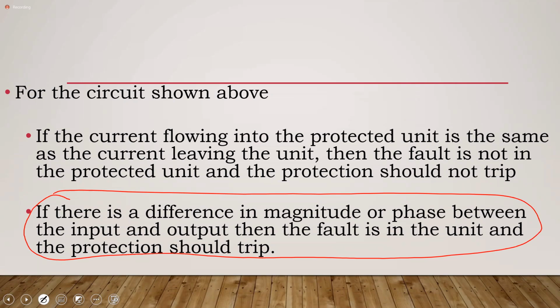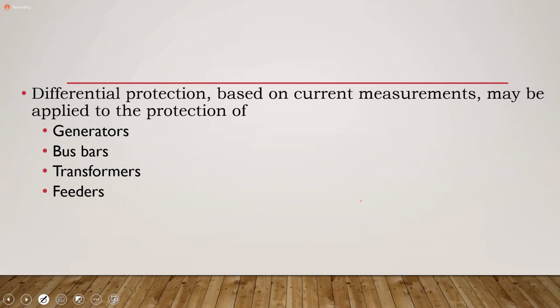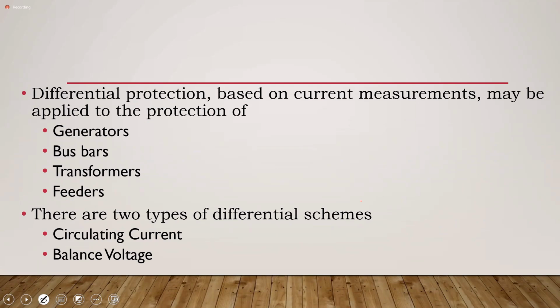Okay? So this is true, but we have to bear in mind that the operation of our equipment has to be considered when making the final decisions. All right. So your differential protection, as I said, looks at current measurements and may be applied to your generators, your bus bars, your transformers, your feeders. And if you recall, when we were looking at the bus bar arrangements, we didn't go into detail about it, but we were restricted in terms of the type of protection that can be applied to your bus bar, based on the arrangement. You have two types of differential schemes.